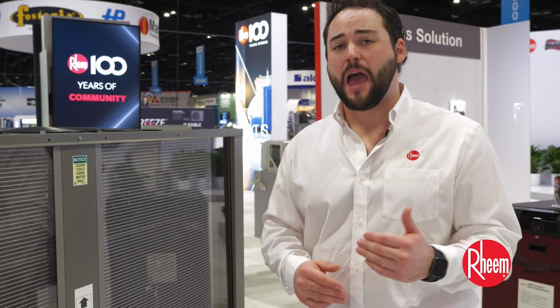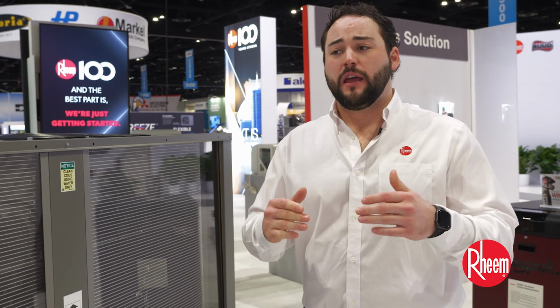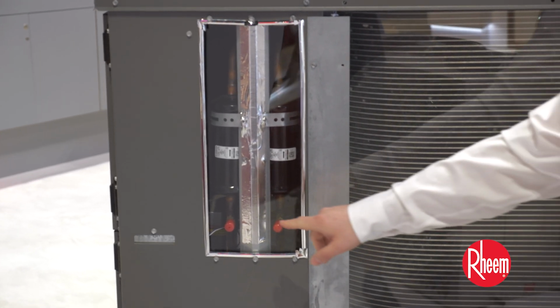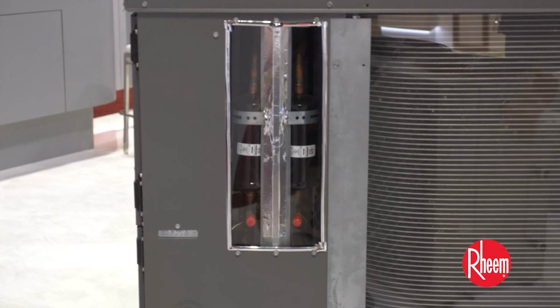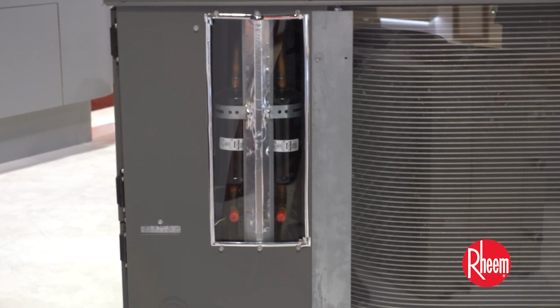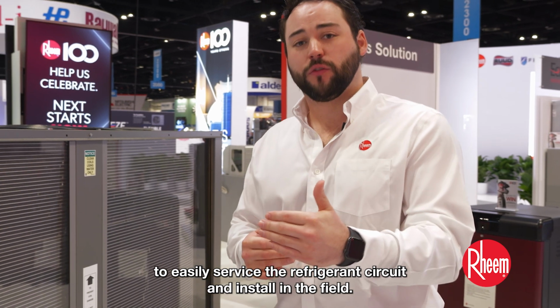What tends to happen is when a contractor does that, it can give them false readings or inaccurate readings on the refrigerant circuit. So we have actually not only put A2L stubs on here to say that it is an A2L refrigerant, which is what the red stubs represent, but the contractor is able to easily service the refrigerant circuit and install in the field.